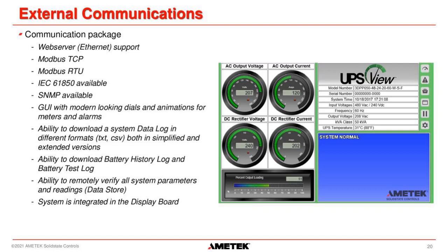We also have the ability to monitor remotely all the readings and values that are available on the HMI if you're in front of the UPS. It's integrated into the display board, but it uses a separate module to isolate any external communications from our UPS. So say somebody tries to hack into the web interface. The web interface will stop working, but the UPS will go on as normal, except that you will get an alarm that says you've lost communication with the Ethernet.